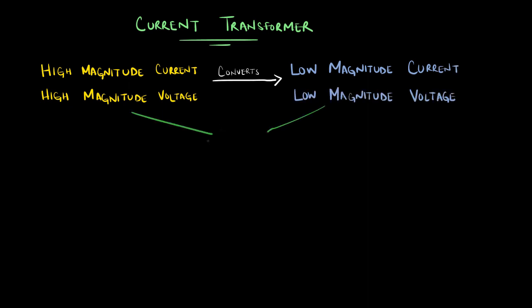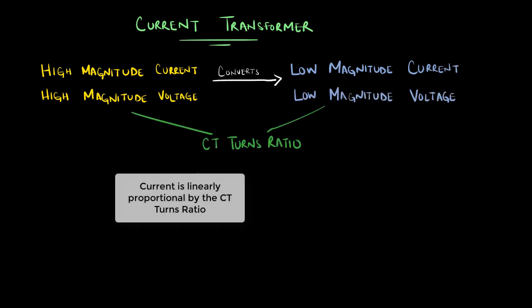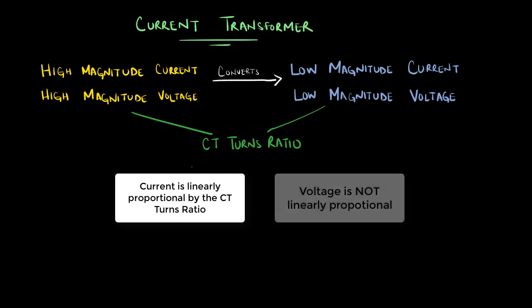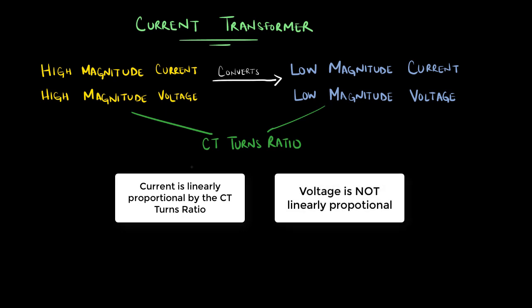The high voltage and low voltage current quantities are linearly proportional by the CT turns ratio during normal operating conditions. Although the voltage quantity on the low voltage side is smaller, it is not linearly proportional. So current transformers are used for step down current quantities.